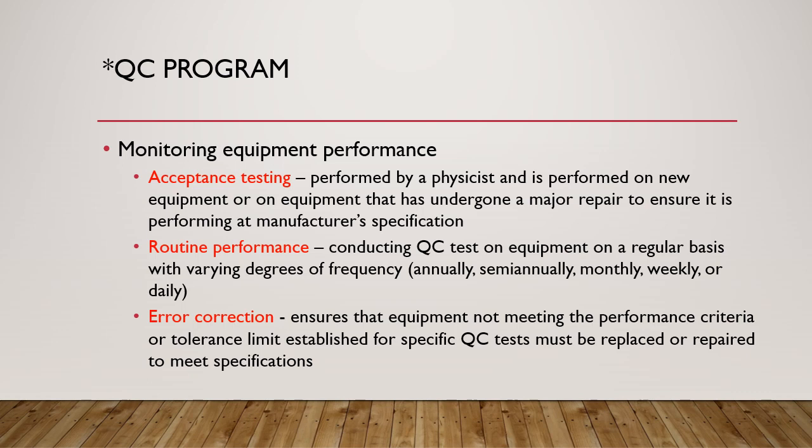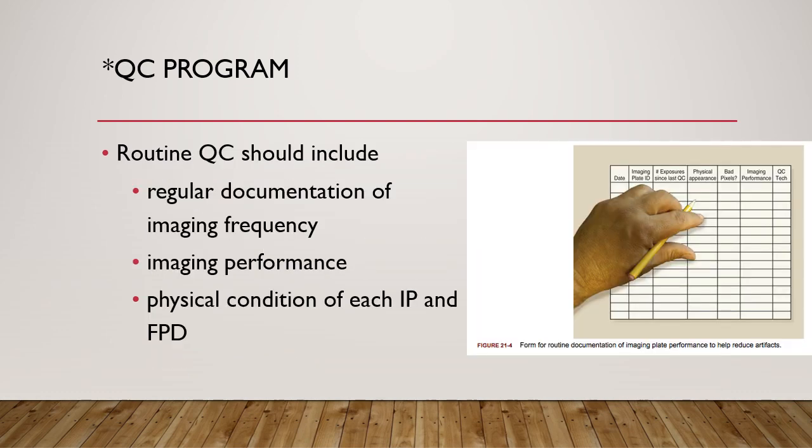And finally, error correction, which ensures that equipment not meeting the performance criteria or tolerance limit established for specific QC tests must be replaced or repaired to meet specifications. QC tests should include regular documentation of imaging frequency, imaging performance, and condition of each imaging plate and flat panel detector.